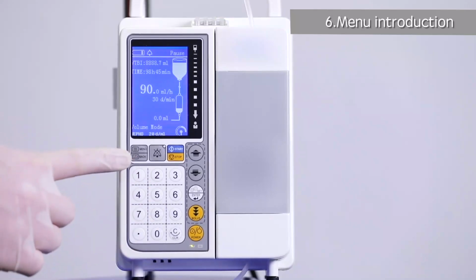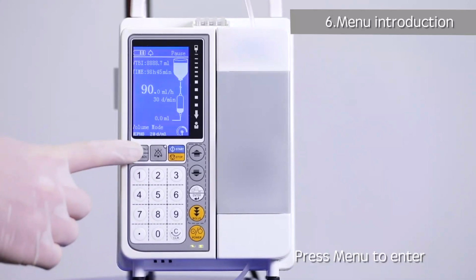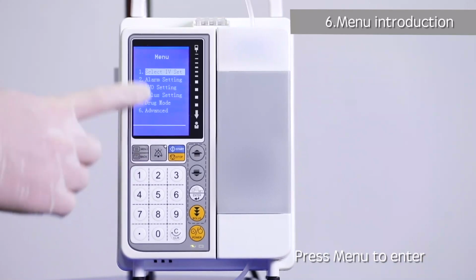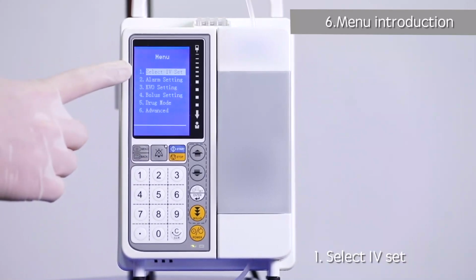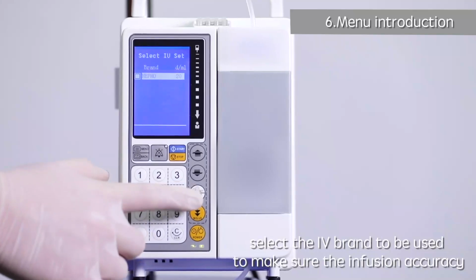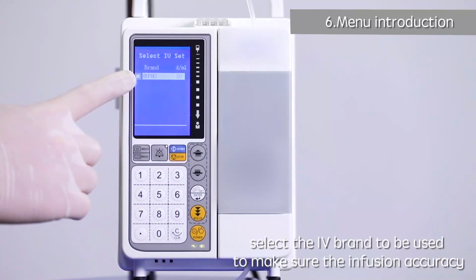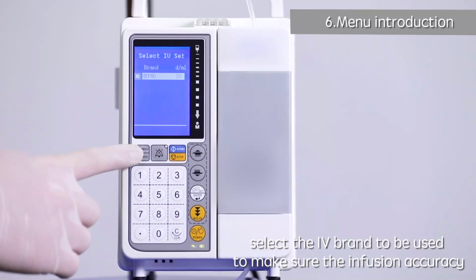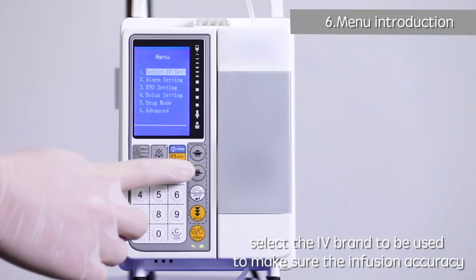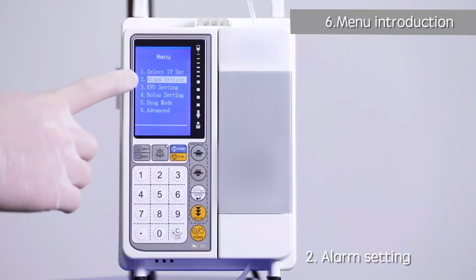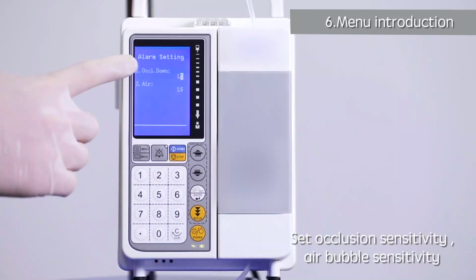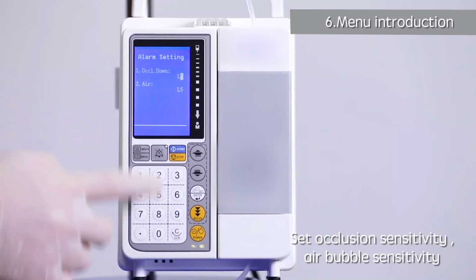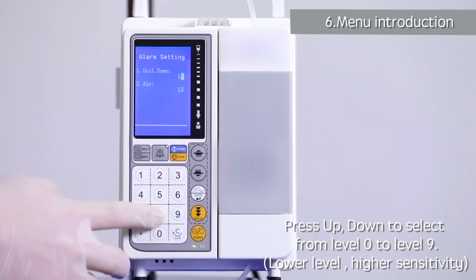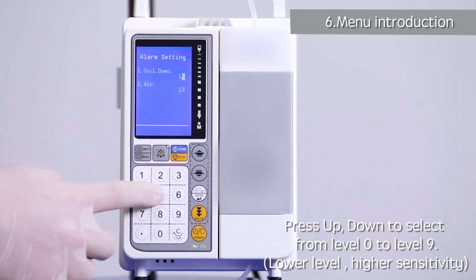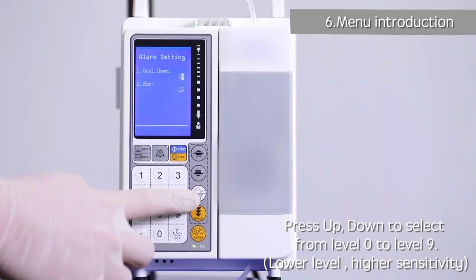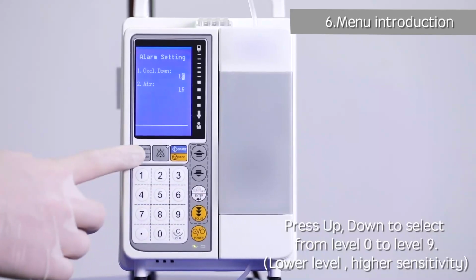6. Menu introduction. Press menu to enter. 1. Select IV set. Select the IV brand to be used to measure the infusion accuracy. 2. Alarm setting. Set occlusion sensitivity and air bubble sensitivity. Press Up, Down to select from level 0 to level 9. Lower level, higher sensitivity.